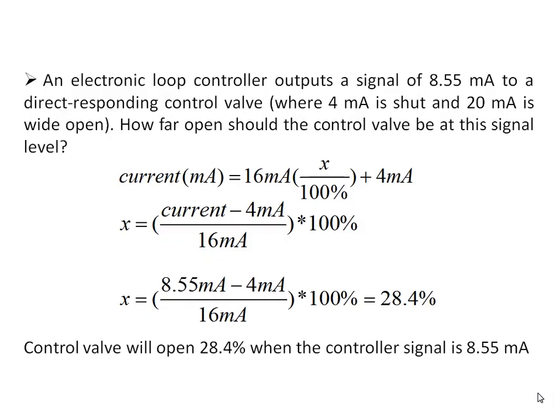Consider this example: an electronic loop controller outputs a signal of 8.55 mA to a direct-responding control valve, where 4 mA means the valve is completely shut and 20 mA means it is completely open. How far is the valve open for a signal of 8.55 mA? Using the equation — current = 16 mA × percentage variable + 4 mA — and substituting 8.55 mA, we get a manipulating variable of approximately 28.4%. So the control valve will open 28.4% when the controller outputs 8.55 mA.